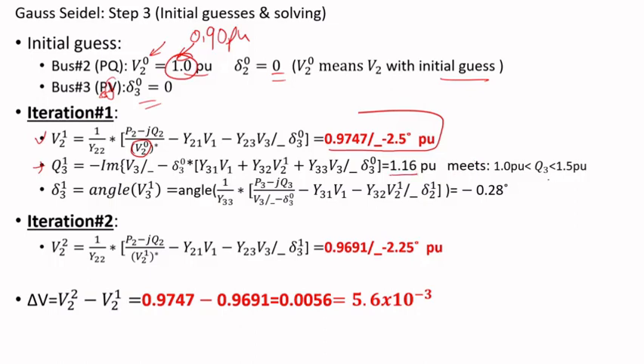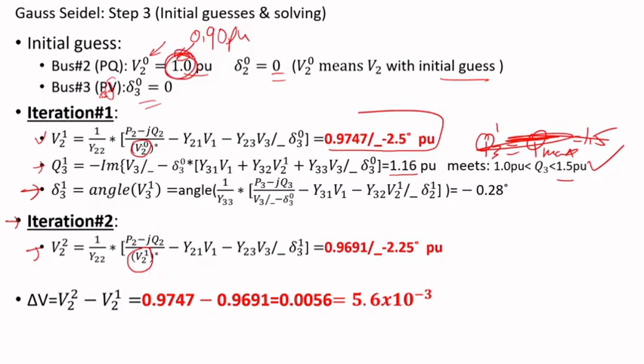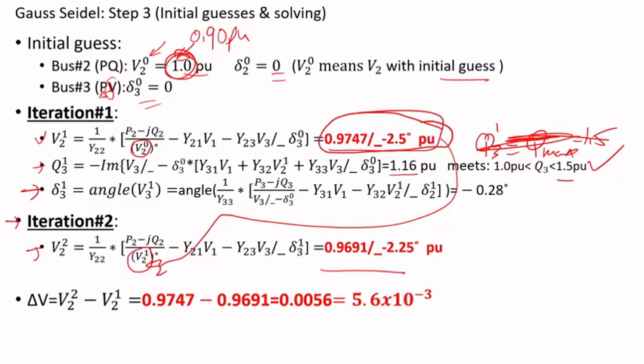The calculated Q₃ = 1.16 p.u., which is below the 1.5 p.u. limit, so Q_max is not triggered. The angle is then calculated. For iteration 2, instead of the initial guess, the previously calculated voltage is used in the equation. The voltage values continue to change but the differences get smaller each iteration, indicating convergence toward the solution.